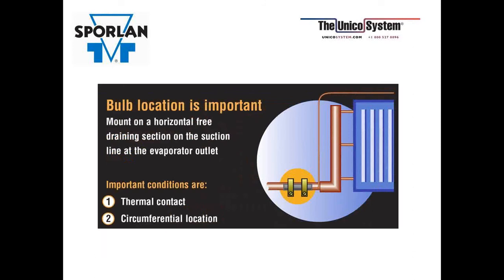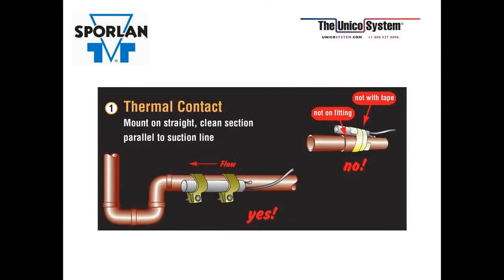Installation tips. You're talking about the bulb mounted on a horizontal free draining section of the suction line at the evaporator outlet. And the 2 things you want to look at there is the thermal contact and the location on the circumference of the pipe. The thermal contact, you want to mount it on a straight, clean section parallel to the suction line. You don't want to go beyond, like on a bend, where half the bulb is hanging into the ambient condition. You want to make sure it's touching the entire length of good, clean tubing, not across a fitting, and not with tape. You want to make sure you use the straps that are supplied in the valve box when you get it. They come with the box. Don't throw it away. And zip ties are also not recommended.